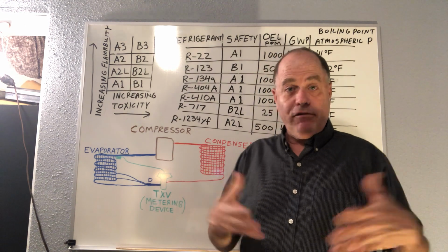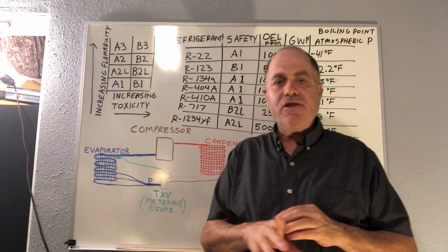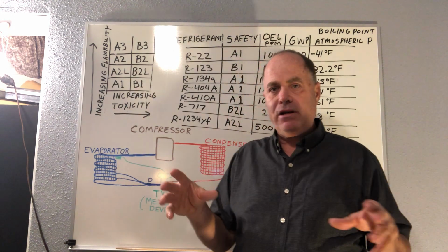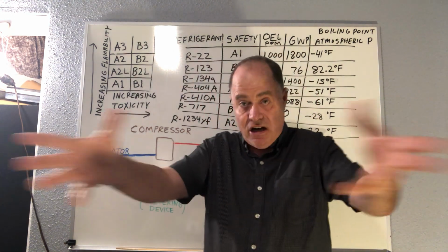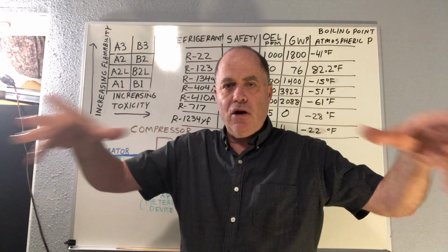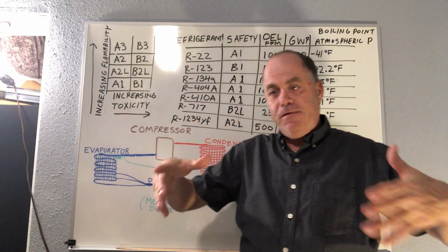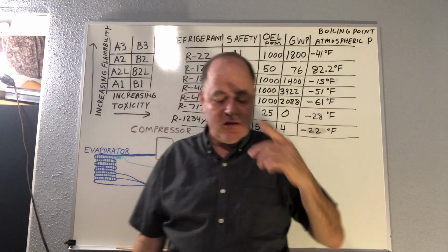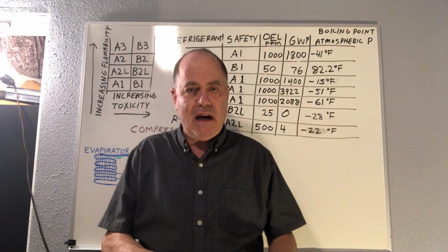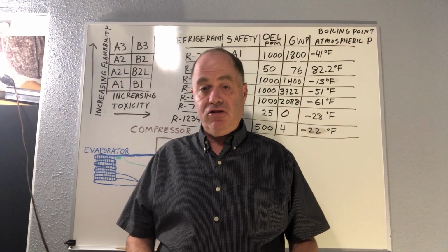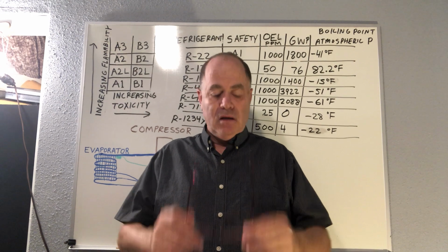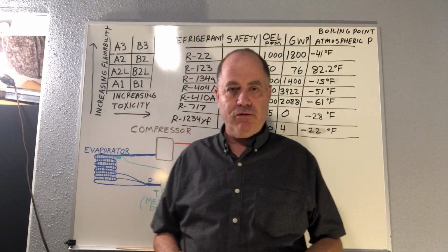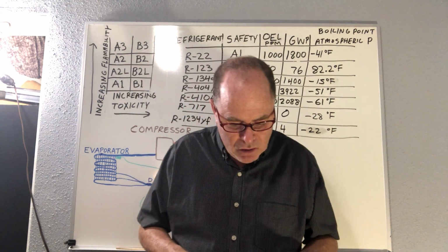And we don't want to use refrigerant for something like that for 2 reasons. If you have a leak, obviously refrigerant costs a lot more than water. And also, think of one of those 50 coils, like if you had 1,000 pounds of refrigerant and that evaporator leaked out into the ductwork, and then where do those ducts go? You could fill up a big space over time, like and displace oxygen. So this kind of concept is why we also tend to use chilled water systems to keep the possibility away of a tremendous amount of refrigerant getting into the occupied space. Okay.